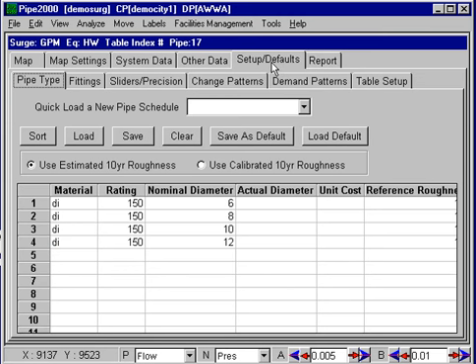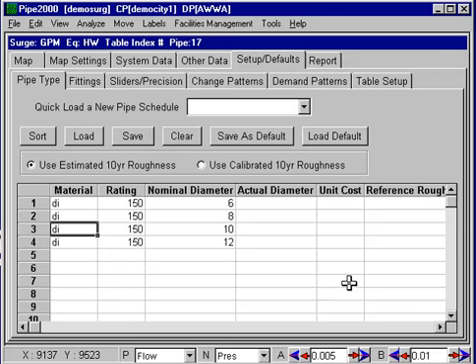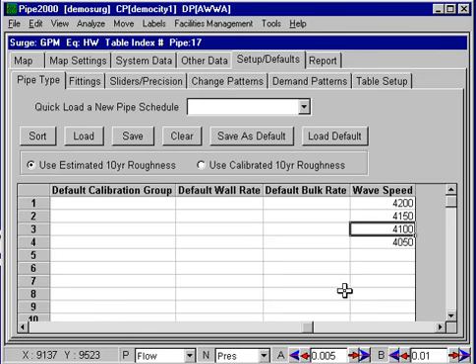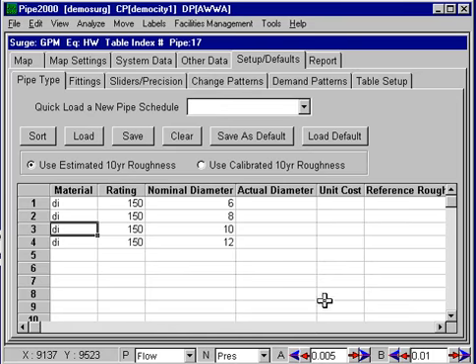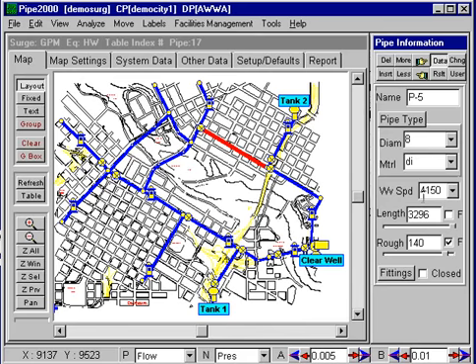If we look at the pipe type table here, we can scroll over to the end and we'll see that there are wave speeds for each of these pipes. So when we select this ductile iron 10-inch pipe, the appropriate wave speed will be entered. That's the best way. If you haven't done that, then you'll have to make sure that you enter the wave speed on this screen manually.